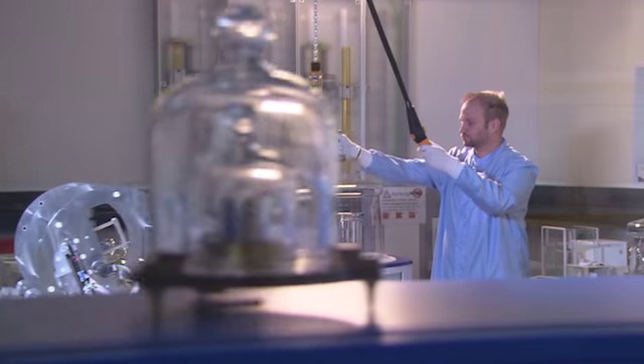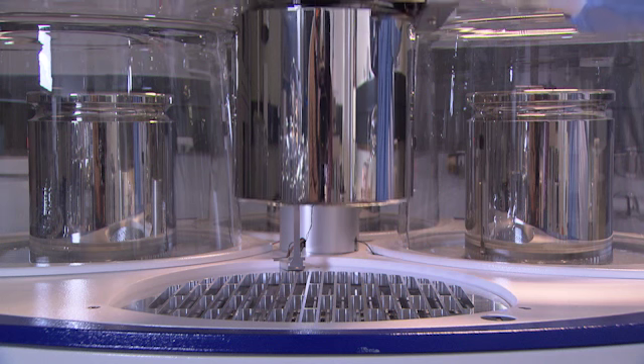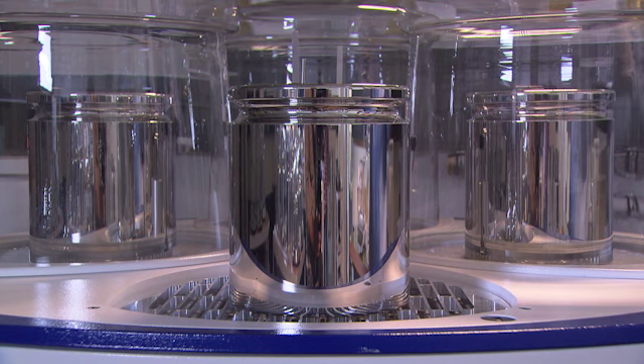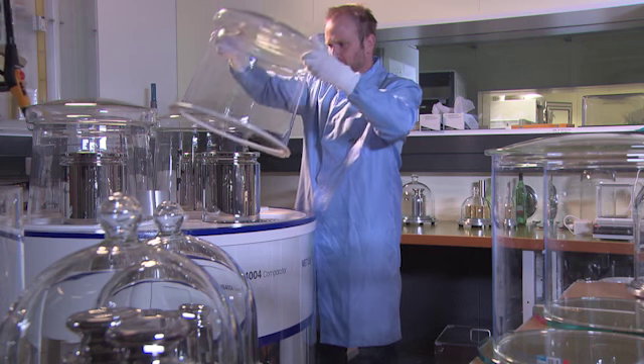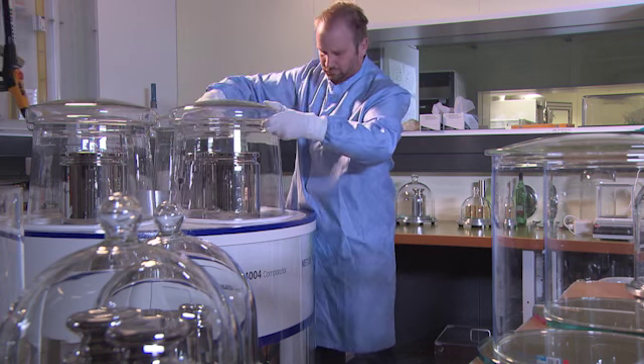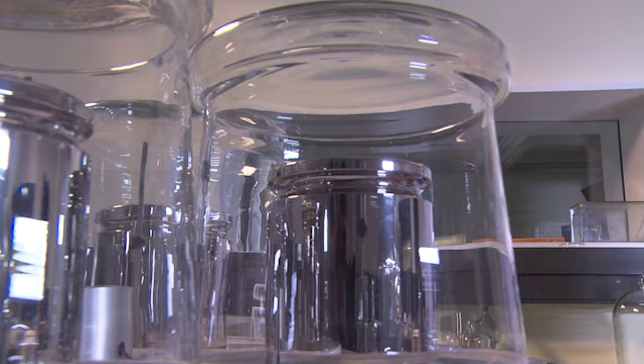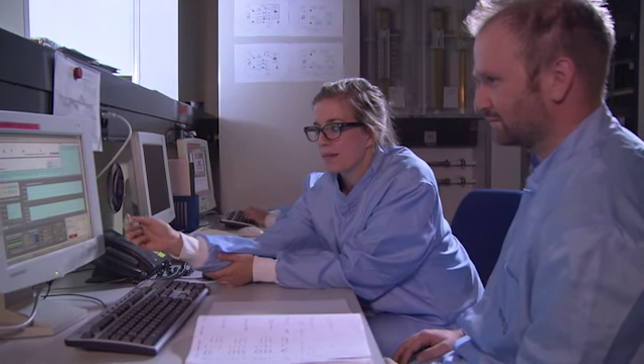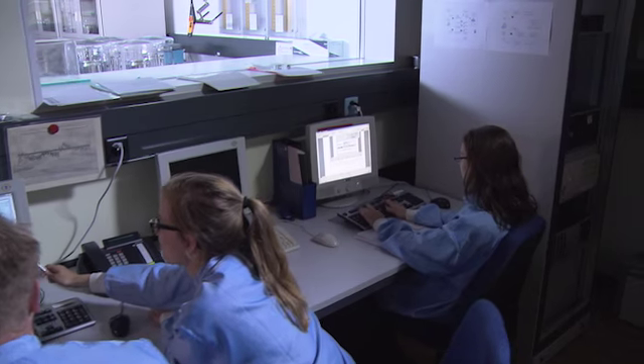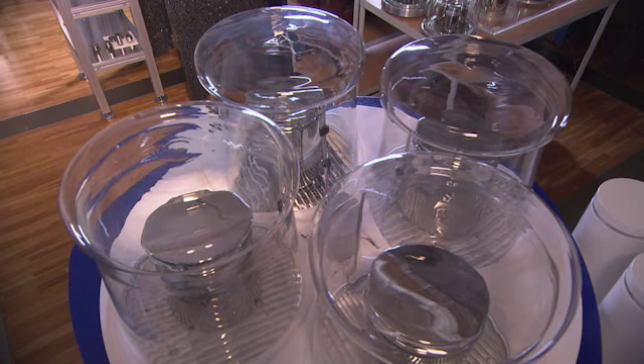To do this, the calibration weights are transported to METAS in Bern, where they're compared to the national reference weights kept there. These comparison measurements are carried out using a high-precision scale known as a mass comparator. The national reference weights, in turn, are compared to a copy of the world's supreme mass reference, the International Prototype Kilogram. This makes it possible to determine and correct calibration errors that might arise.